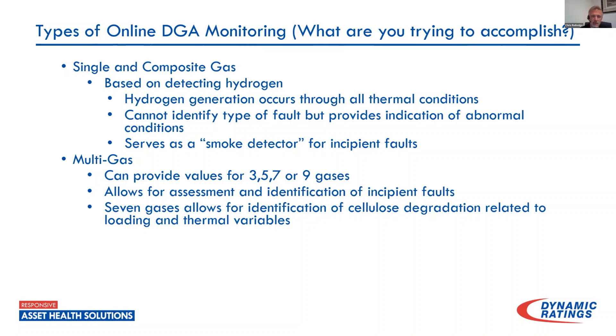With multi-gas monitoring, you can have three, five, seven, or nine gases depending on how much detail you want. It does allow for assessment and identification of faults — I can look and say I've got a really good arcing signature, or I've got PD that is worsening and I'm starting to see development of ethane and then ethylene. With seven gases we get into carbon monoxide and carbon dioxide, which gives me a good idea about cellulose degradation — how much thermal damage am I doing to my solid insulation systems.